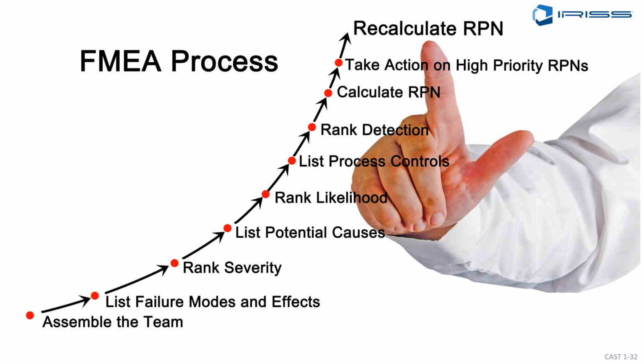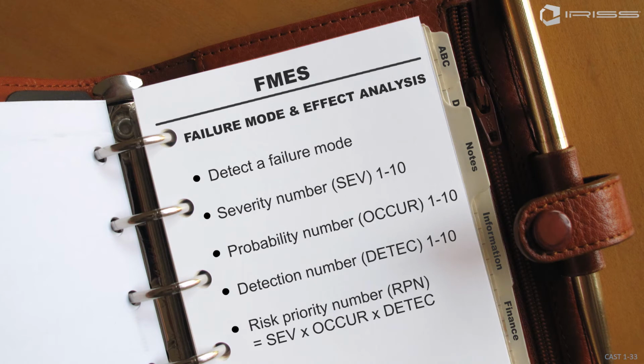So the final part, electrical maintenance now is very heavily risk orientated. And one of the things we have to calculate when we're looking at failure modes effects analysis processes is something called an RPN, or a risk priority number. Now this risk priority number, typically, there are different ways of calculating this, but this is the most used. We typically use 3 areas. We look at the severity, i.e. the severity of failure from 1 to 10, and anything affecting life or limb would always be a 10. But the severity is based on business risk, human risk, financial risk, whichever drives your facility.